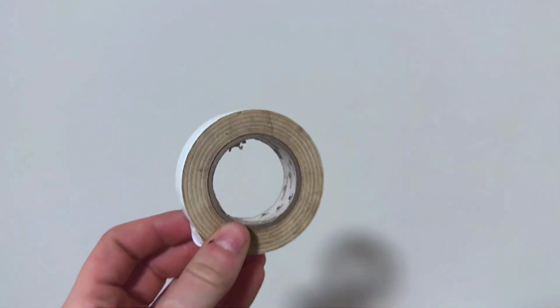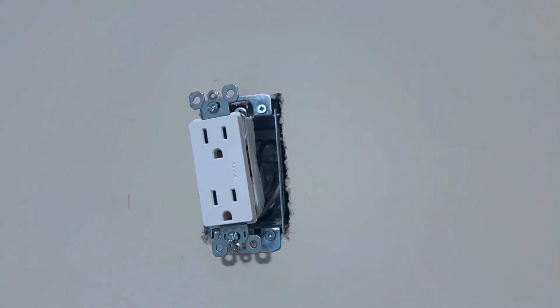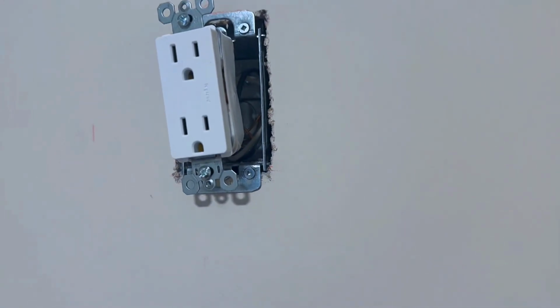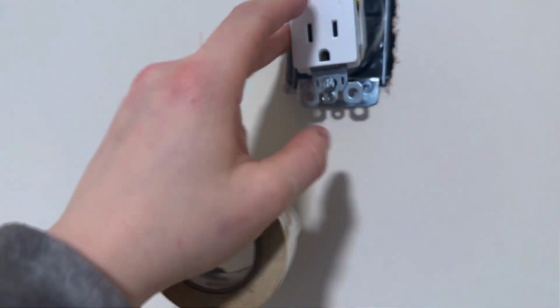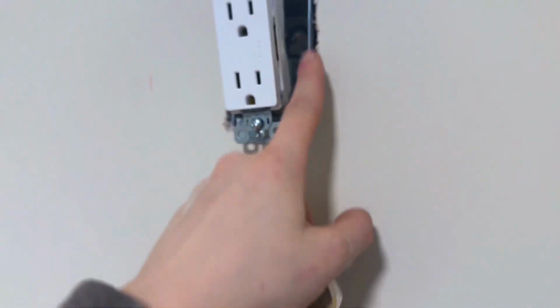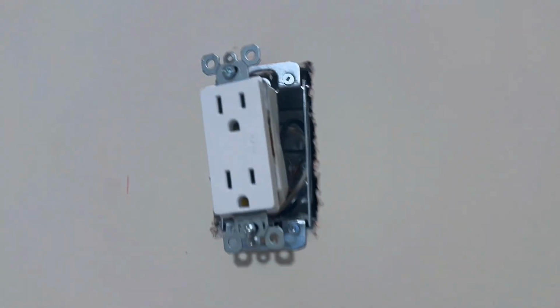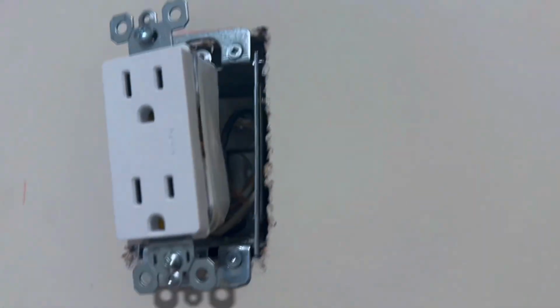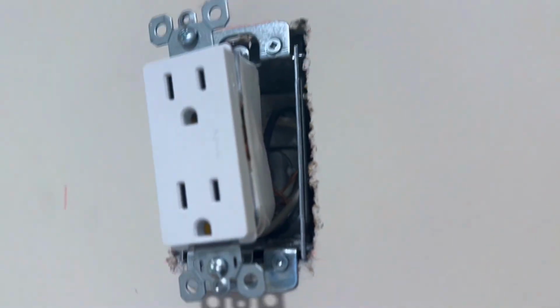Next step after you have the terminals done is tape. Because this receptacle is inside of a metal box, the box is conductive. So if any of these screws here, if this hot screw here touches this box, it's gonna blow up on you. After you've done that, let's screw the receptacle in, put our cover plate on, and power up this circuit.